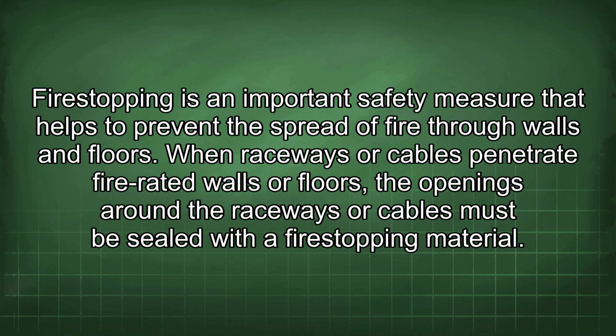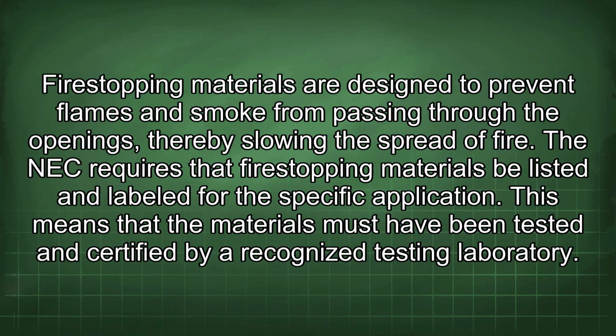Fire stopping is an important safety measure that helps to prevent the spread of fire through walls and floors. When raceways or cables penetrate fire-rated walls or floors, the openings around the raceways or cables must be sealed with a fire-stopping material. Fire-stopping materials are designed to prevent flames and smoke from passing through the openings, thereby slowing the spread of fire. The NEC requires that fire-stopping materials be listed and labeled for the specific application. This means that the materials must have been tested and certified by a recognized testing laboratory.